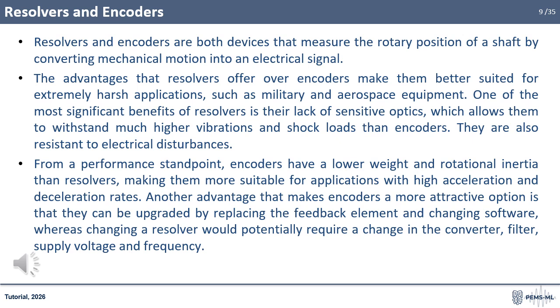From a performance standpoint, encoders have a lower weight and rotational inertia than resolvers, making them more suitable for applications with high acceleration and deceleration rates. Another advantage that makes encoders a more attractive option is that they can be upgraded by replacing the feedback element and changing software, whereas changing a resolver would potentially require a change in the converter, filter, supply voltage, and frequency.